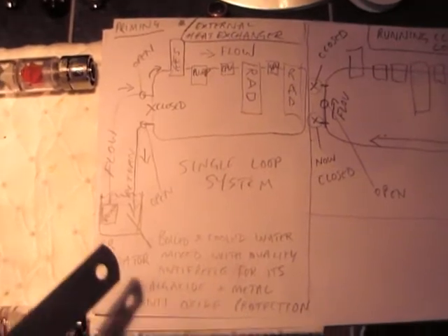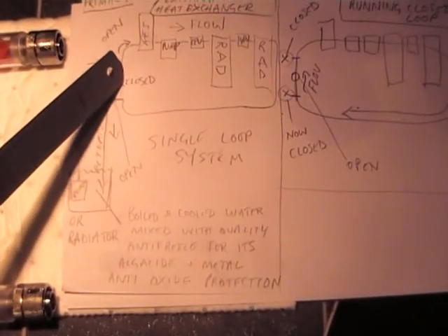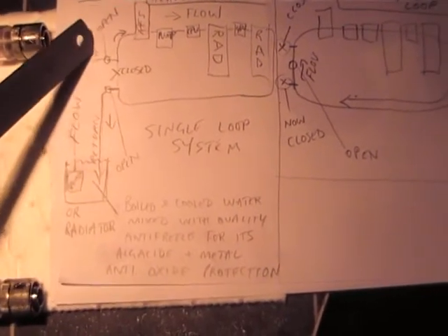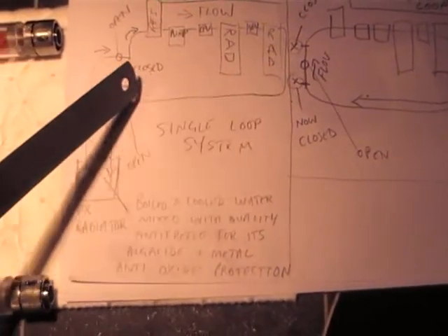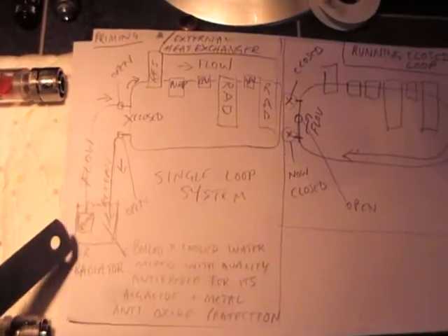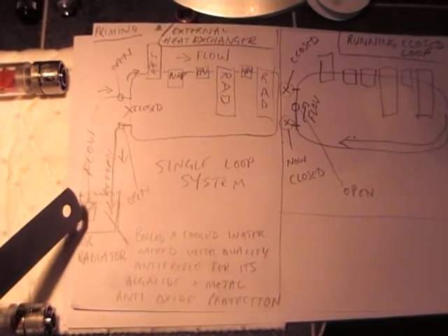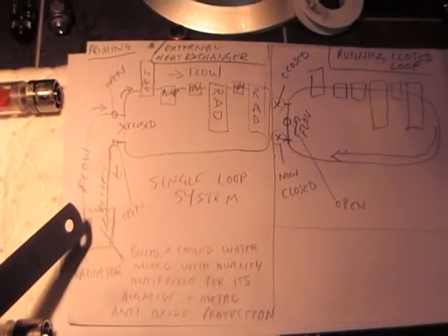So if you want to fill the system then this center one is closed. These two valves are opened. Your flow goes round through the system, back down again. So you could use this if you wanted to use an external radiator, or if you wanted to blow the air out of the system.